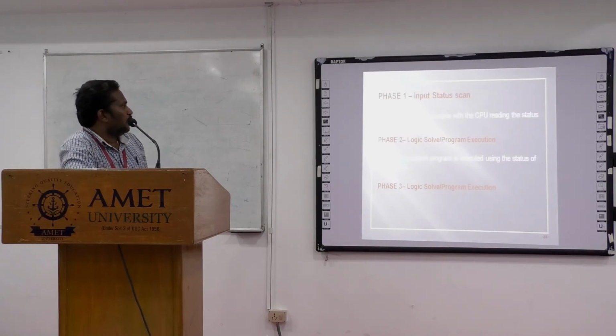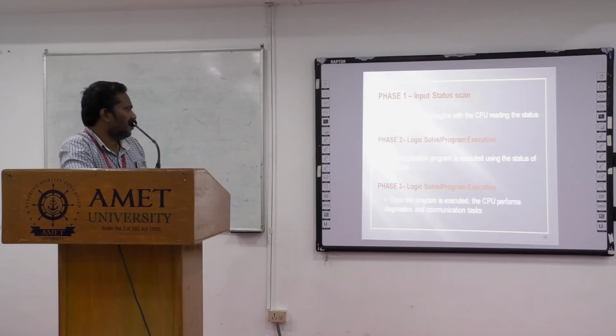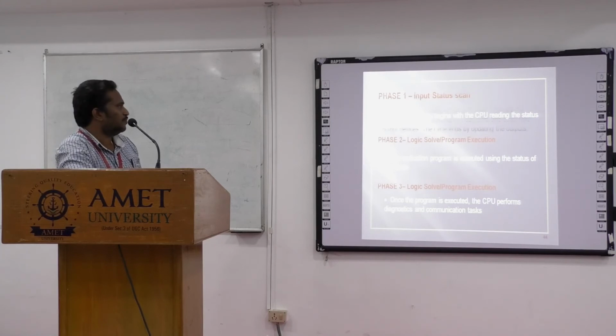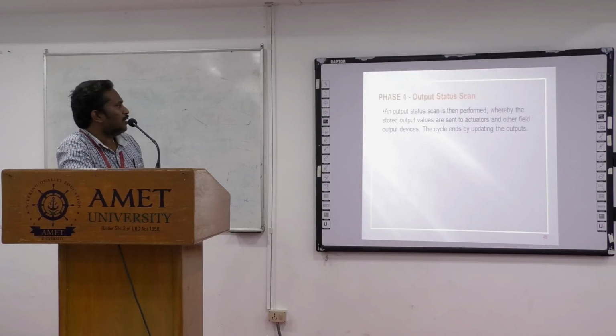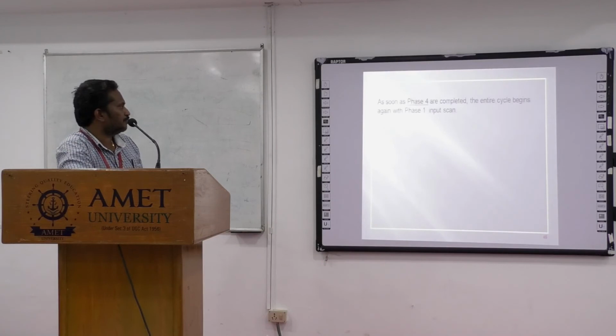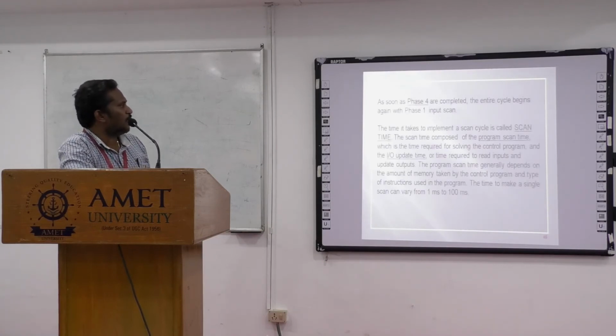So phase 1, the input scan. A PLC scan cycle begins with the CPU reading the status of its inputs. Phase 2, the application program is executed using the status of the inputs. Phase 3, once the program is executed, the CPU performs diagnostics and communication tasks. An output status scan is performed at last, whereby the stored output values are sent to the actuators and the other field output devices. The cycle ends by updating the outputs. As soon as phase 4 is completed, the entire cycle begins again with phase 1, the input scan.